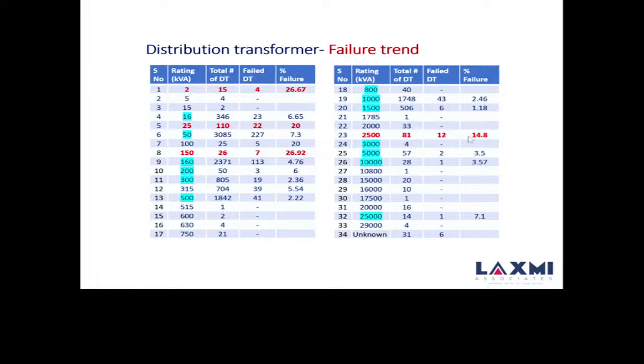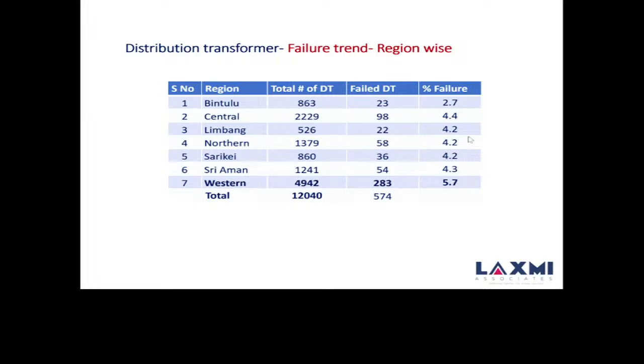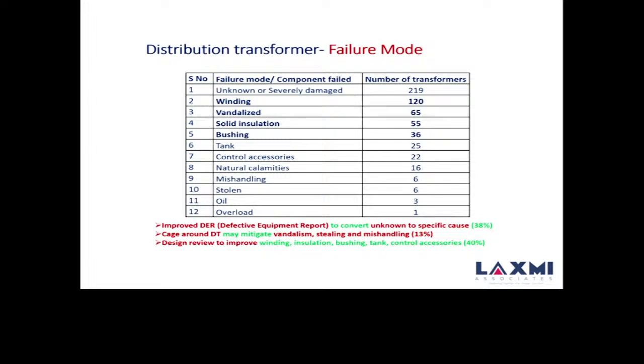We find that rating-wise, the failure trend is high for some ratings, marked in red at 26%, 20%, and so on. Region-wise also, the failure rate is high for some regions, particularly industrial belts. This is about 12,000 distribution transformers in the fleet I'm talking about.